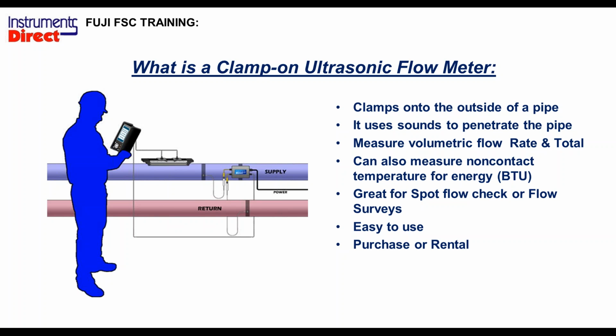So as you can imagine, there are many, many advantages of having an opportunity to monitor flow with this ease. To operate this device, it uses sound or ultrasonic frequencies to penetrate the pipe wall and into the liquid. It measures volumetric flow, total flow, and velocity. But for most people, they want to monitor how many gallons per minute they have and how many gallons they use today. You can also monitor energy. You can add non-contact temperature to the equation. So that's for the advanced users.